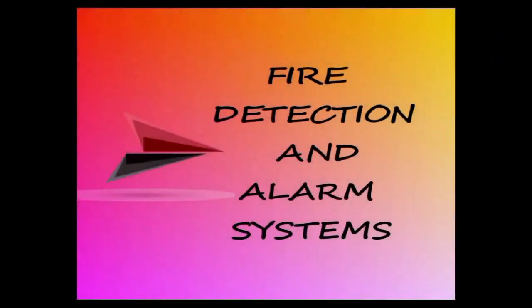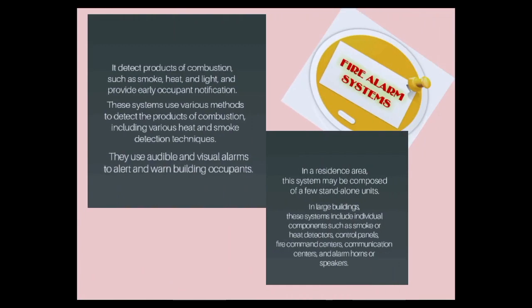Fire detection and alarm systems. Fire alarm systems detect products of combustion such as smoke, heat, and light and provide early occupant notification. These systems use various methods to detect the products of combustion, including various heat and smoke detection techniques. They use audible and visual alarms to alert and warn building occupants. In a residence, this system may be composed of a few standalone units. In large buildings, these systems include individual components such as smoke or heat detectors, control panels, fire command centers, communication centers, and alarm horns or speakers.